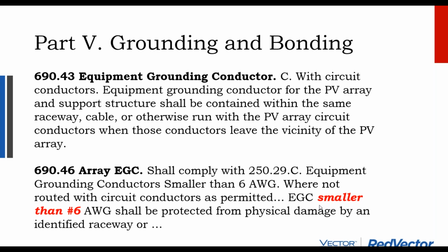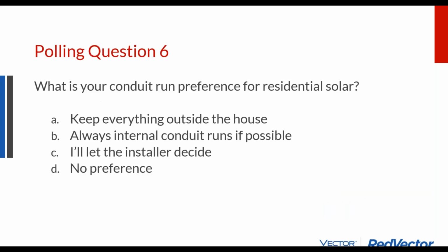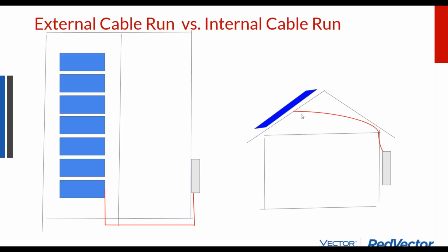My preferred method is a little bit different than that. And we're not going to get into this polling question in the interest of time, but the question is, do you want to keep all the solar conductors outside the house, or do you want to run the conductors inside the house? My preference is to run the conductors through the attic down to the service panel rather than run the conductors outside the house. The reason is it's often more direct to go just into the attic and through. And the other reason is I use a cable for the inside the house attic run called MC cable that makes this run expensive, but also quick and easy.